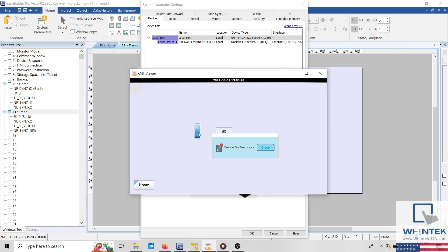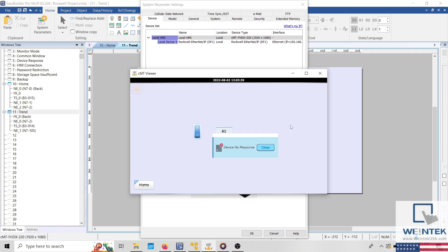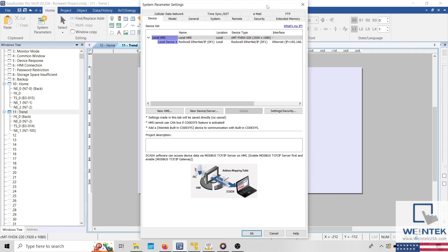But this is in fact an accurate indication that a communication error exists within your project. Now before we switch any cables, reboot the HMI, or make any changes to our current project, I think it's important to review the PLC connection guide that was created for the driver that we're using within our application.